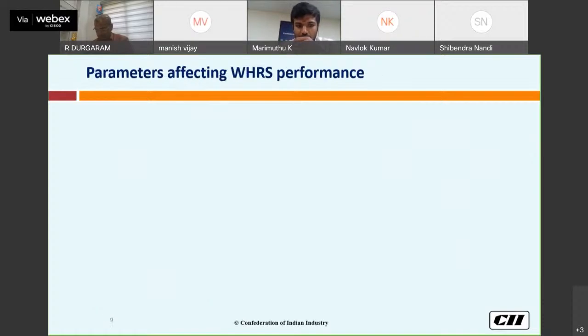Then coming to the parameters affecting the waste heat recovery system performance. The first one is low heat input to the boiler. In some of the units the design megawatt is one, but actually we are generating maybe less or more, and there are some factors which influence the lower power generation. Those are covered in this slide. So the first one which we are going to see is low heat input to the boiler.